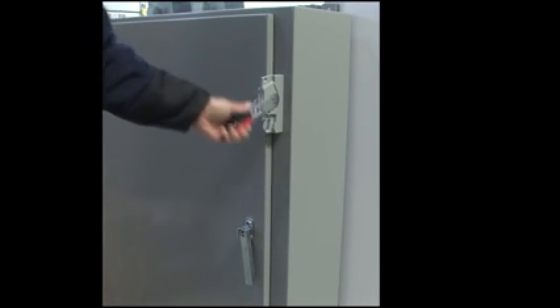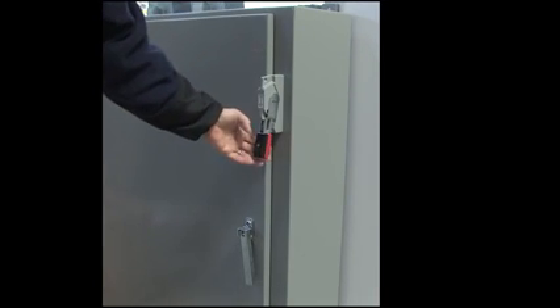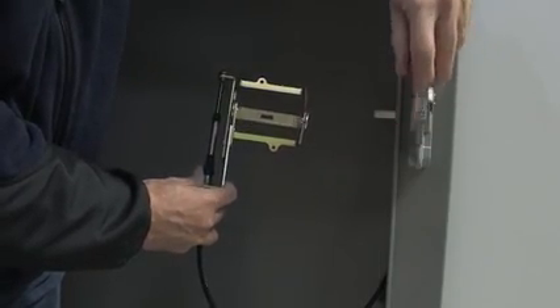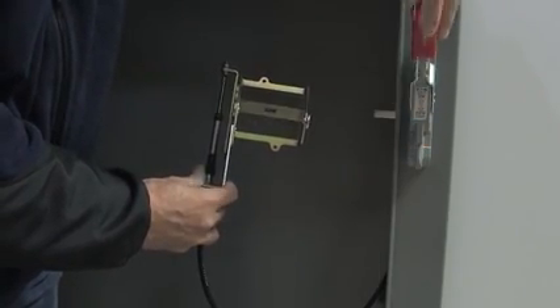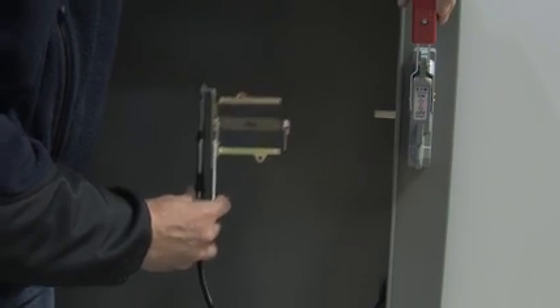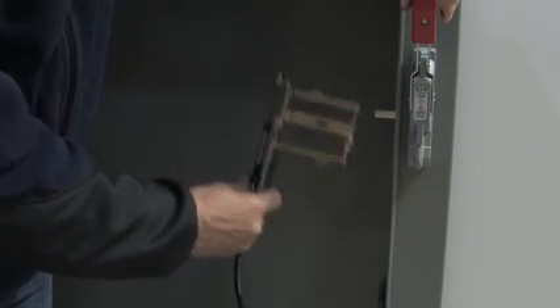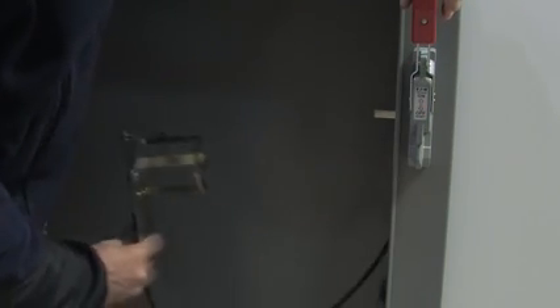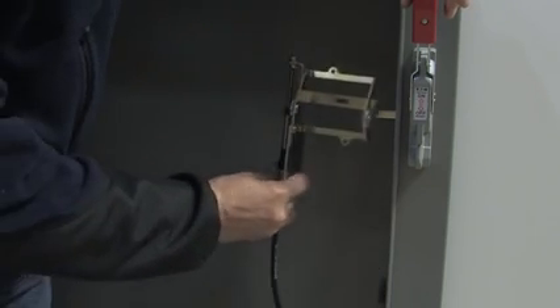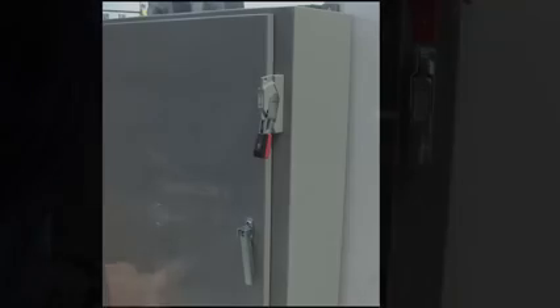The other way is using a flexible handle like this. These work in a cabinet that's specifically pre-drilled for mounting the handle, so it can work in concert with the door latching mechanism. The nice thing about this is you have more flexibility on where you put your circuit breaker in the cabinet. These come with lots of hardware and have built-in adjustments so you can mount them to a variety of breakers. The other nice thing about these guys is you don't have to worry about drilling a hole exactly in the right place to mate up with the circuit breaker.